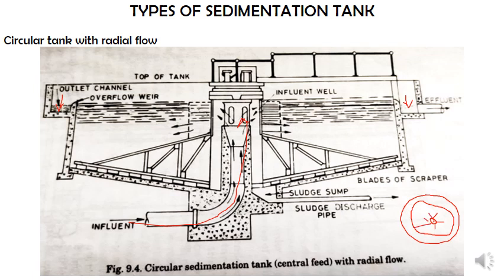And as and when the water enters, you can again see there will be some baffles here. You are seeing all these baffles, right? So what will happen is once this water enters into this chamber, it will hit this baffle, and in turn the water will first go down and then it will rise up. So in this particular process, one of the advantages is, as and when the water is moving in the upward direction at a very slow velocity, even these suspended particles tend to settle down because they don't have any intent of moving in the upward direction.